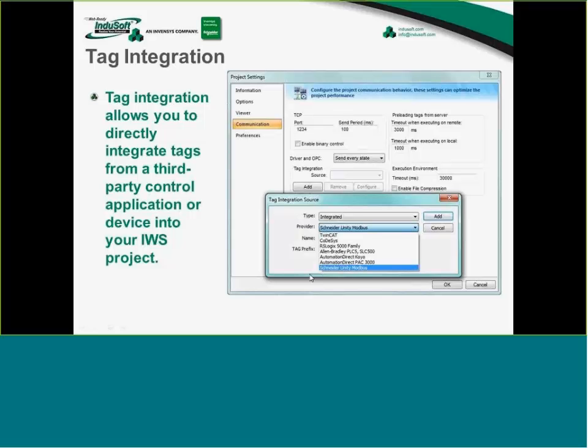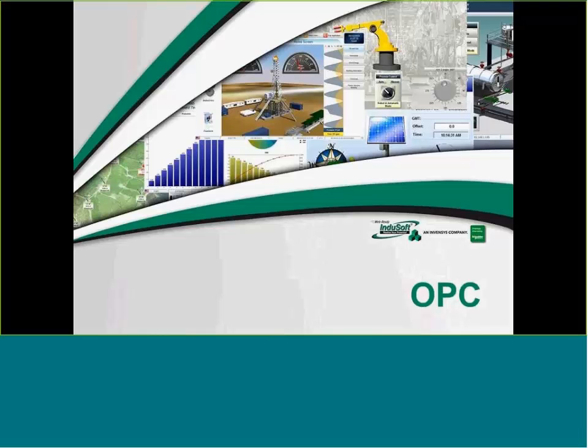Today it's TwinCAT, CODESYS, the ControlLogix is RSLogix 5000 from Allen-Bradley, PLC-5 and SLC, as well as AutomationDirect for the Koyo series and PAC3000, and we even have now a Schneider Unity Modbus in there. And that's basically you pick from the list that is imported, and only the tags that you pick from are the ones that are brought into your applications. The ones that you don't choose don't consume tags.